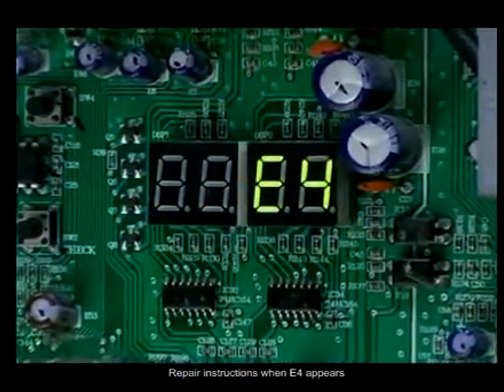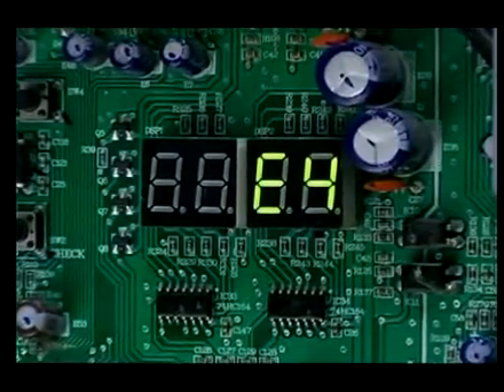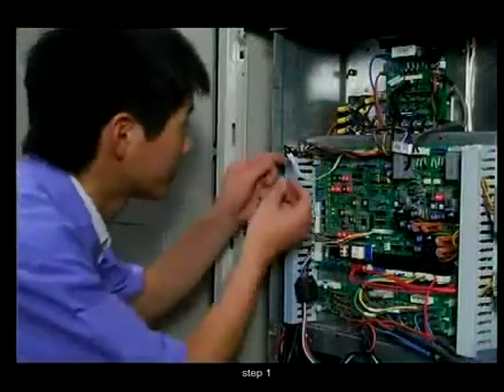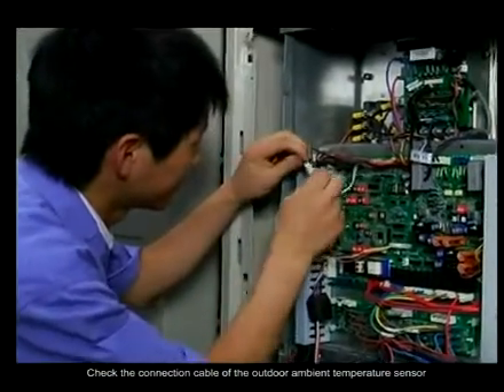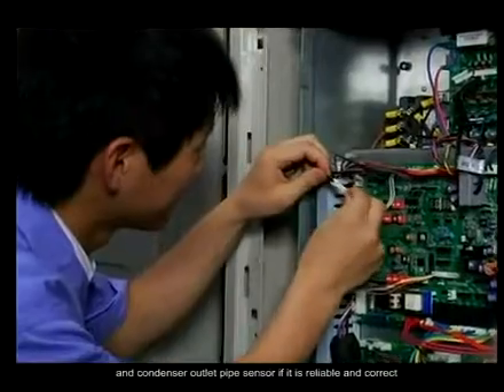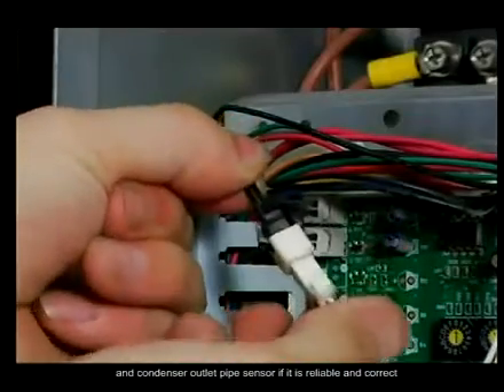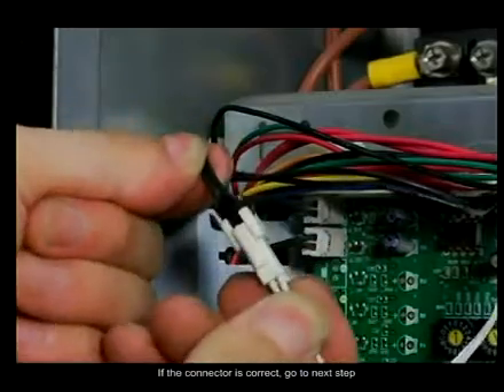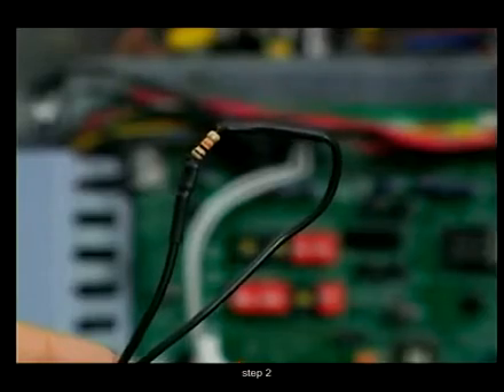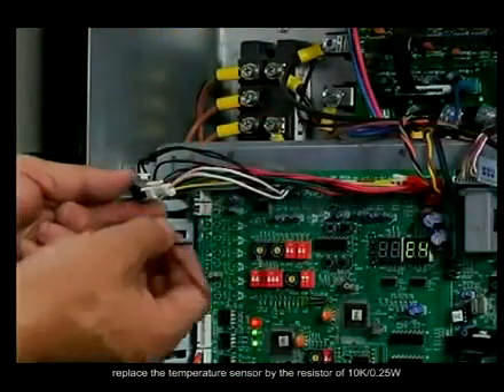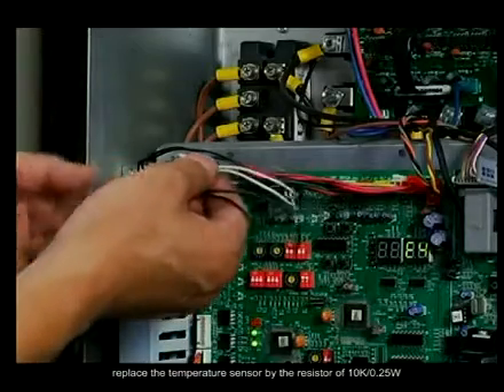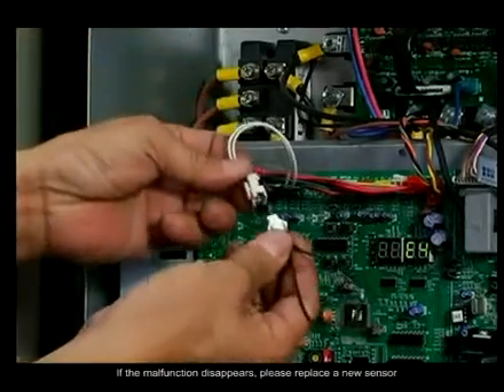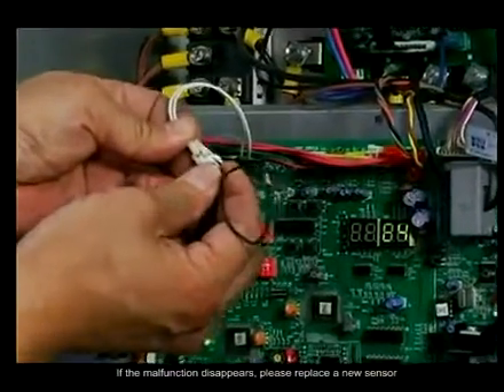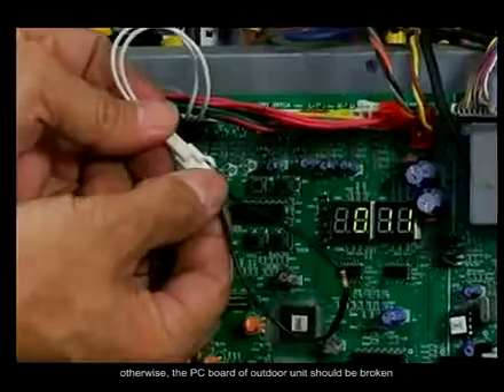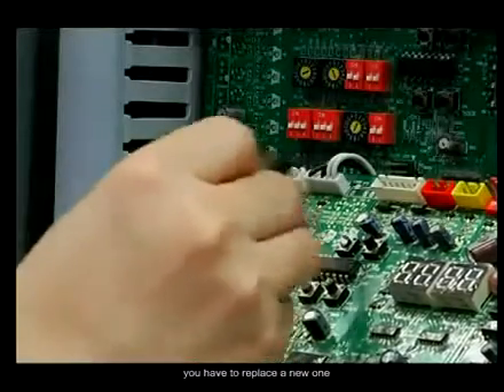Repair instructions when E4 appears. Step 1. Check if the connection cable of the outdoor ambient temperature sensor and condenser outlet pipe sensor is reliable and correct. If the connector is correct, go to the next step. Step 2. Replace the temperature sensor with a resistor of 10K, 0.25 watts. If the malfunction disappears, please replace with a new sensor. Otherwise, the PC board of the outdoor unit may be broken. You have to replace it with a new one.